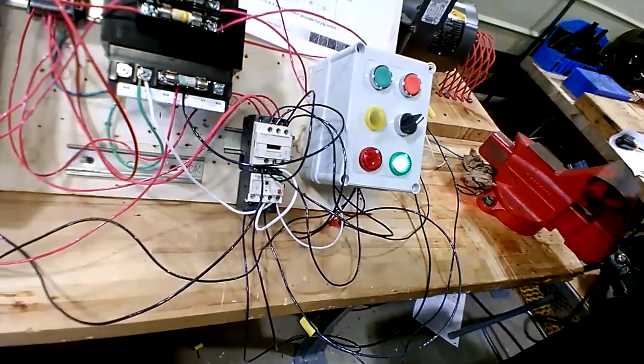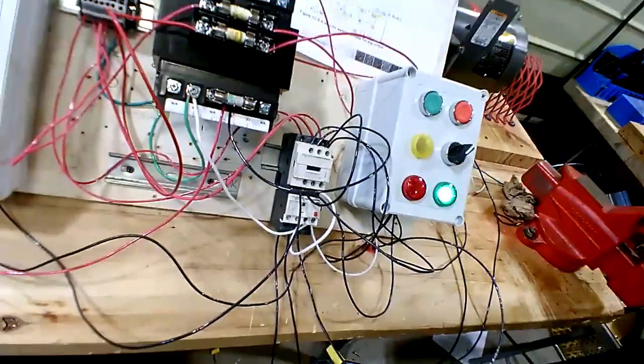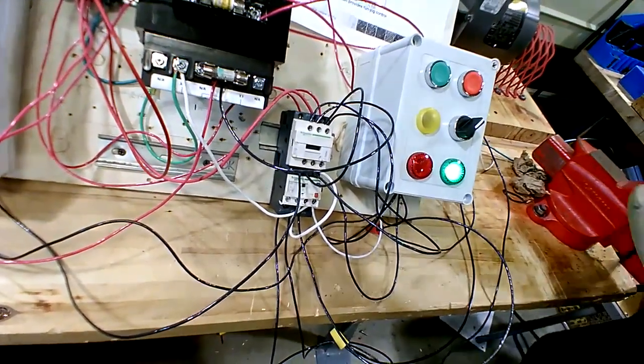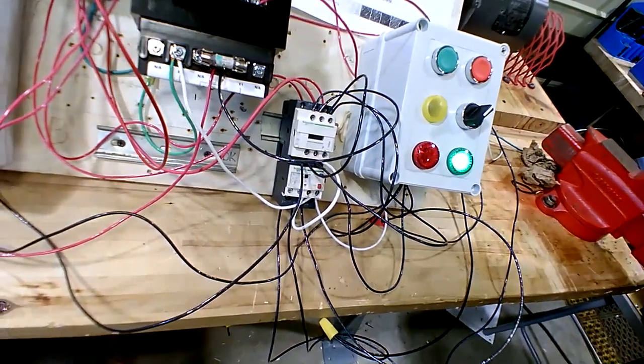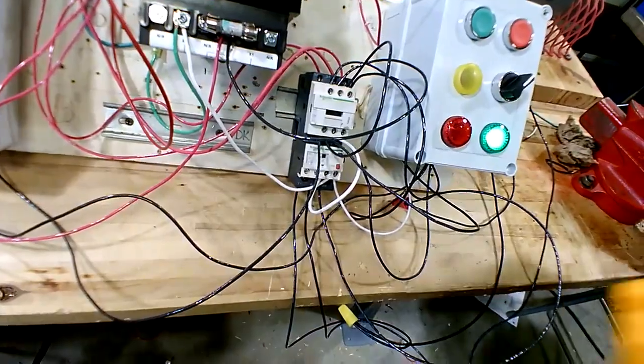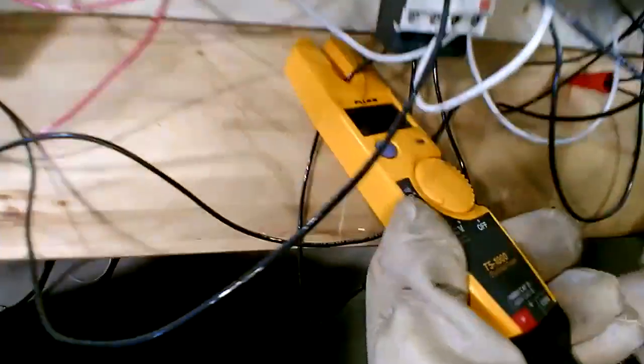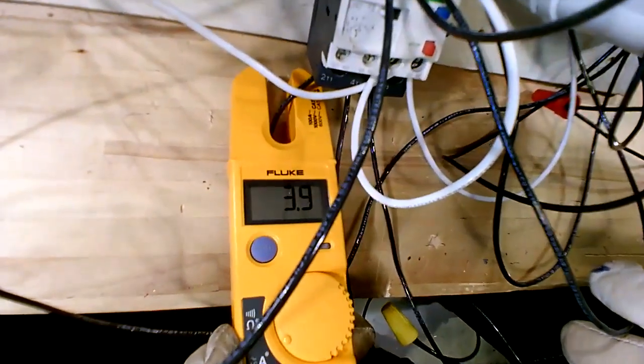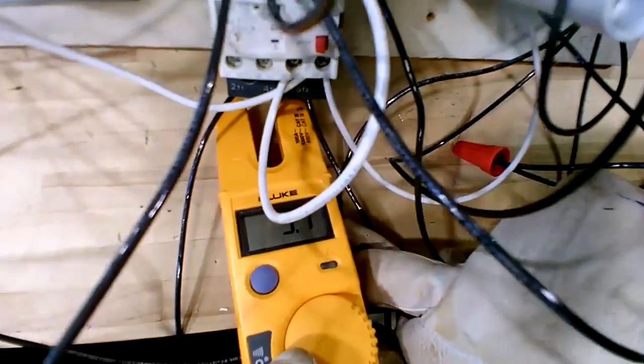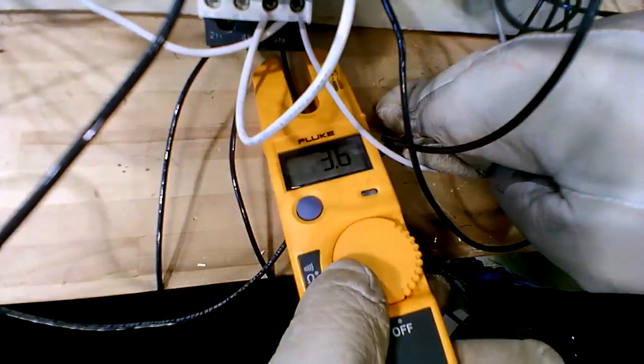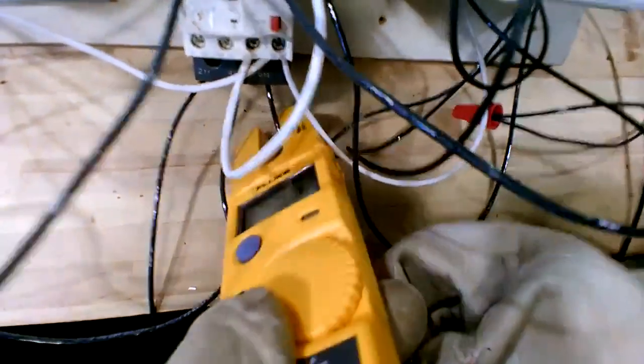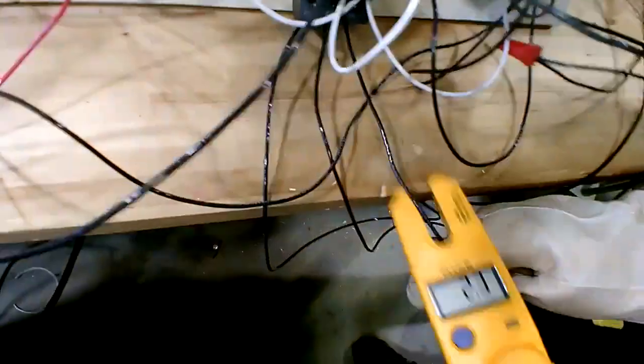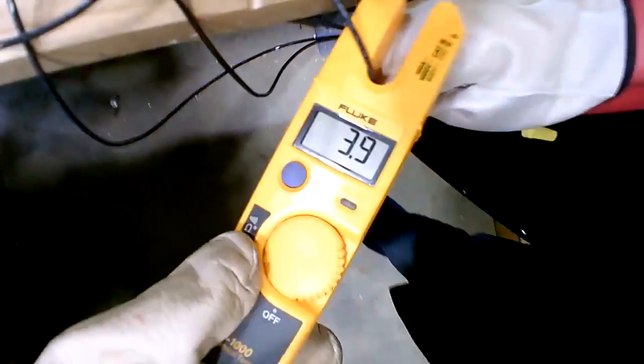So flip it over to A for amps, and you'll use the fork now to check your amps. So you're getting, I can't really read it. What do you get? 3.8 amps. Good. That's for the first leg, second leg. About 3.8 again. Okay. 3.6, or you got to get all the way up in there. Just get in there, be fine. Position it. There you go. 3.9, that's good.